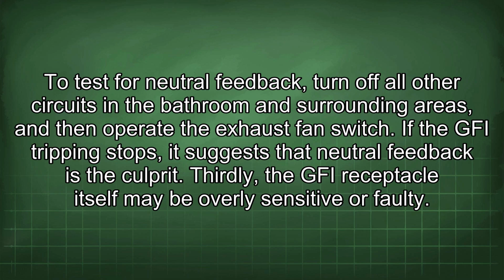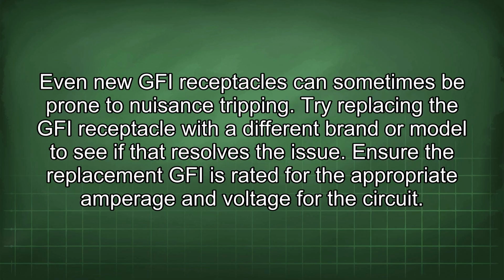Thirdly, the GFI receptacle itself may be overly sensitive or faulty. Even new GFI receptacles can sometimes be prone to nuisance tripping. Try replacing the GFI receptacle with a different brand or model to see if that resolves the issue. Ensure the replacement GFI is rated for the appropriate amperage and voltage for the circuit.